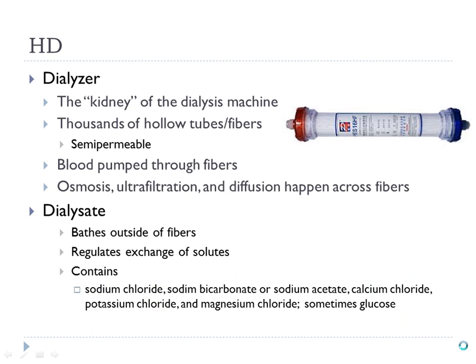The dialyzer is the kidney of the dialysis machine. Inside this tube are thousands of hollow fibers — tiny semipermeable tubes. The blood is pumped through all of those tubes, and the process of ultrafiltration and diffusion happens. All those toxins, electrolytes, urea, and creatinine that the kidneys normally remove are diffused across that semipermeable membrane.